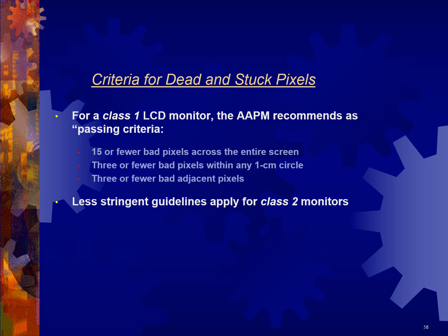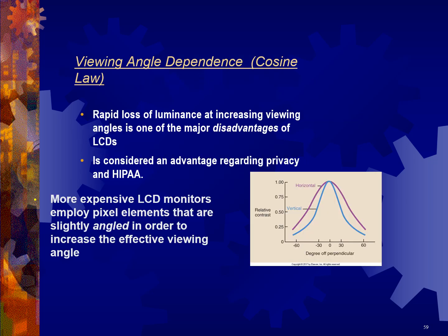It should look consistent across all monitors. So if you see bad pixels that are reporting either just black, or basically null, no value, in a field of uniform gray, you should call in Biomed and have them take a look at it.